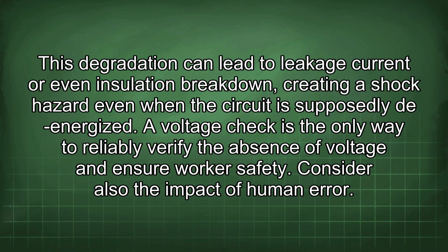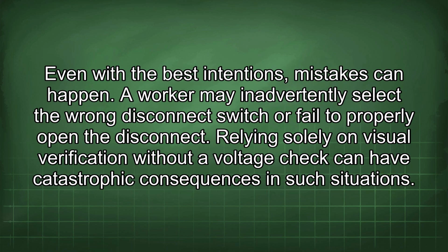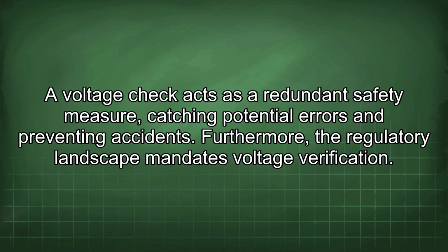Consider also the impact of human error. Even with the best intentions, mistakes can happen. A worker may inadvertently select the wrong disconnect switch or fail to properly open the disconnect. Relying solely on visual verification without a voltage check can have catastrophic consequences in such situations. A voltage check acts as a redundant safety measure, catching potential errors and preventing accidents.